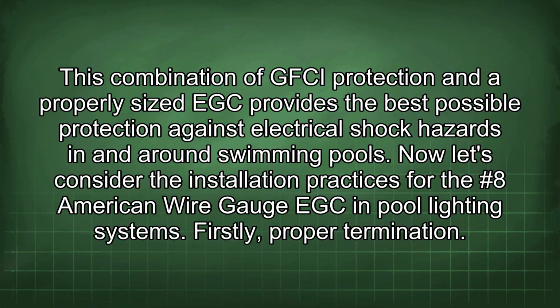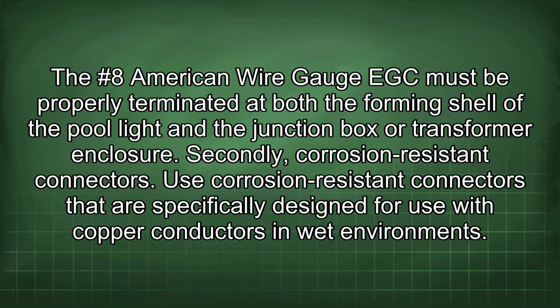Now let's consider the installation practices for the #8 American wire gauge EGC in pool lighting systems. Firstly, proper termination. The #8 American wire gauge EGC must be properly terminated at both the forming shell of the pool light and the junction box or transformer enclosure. Secondly, corrosion-resistant connectors. Use corrosion-resistant connectors that are specifically designed for use with copper conductors in wet environments.